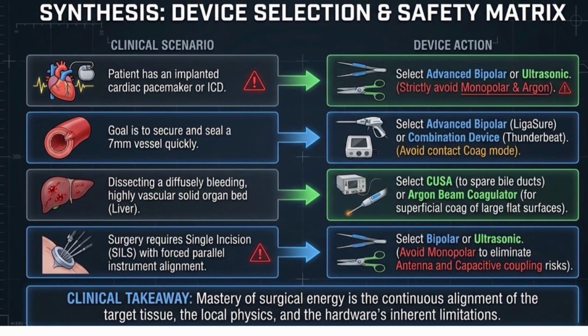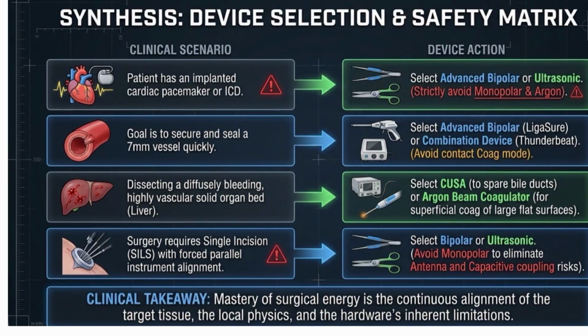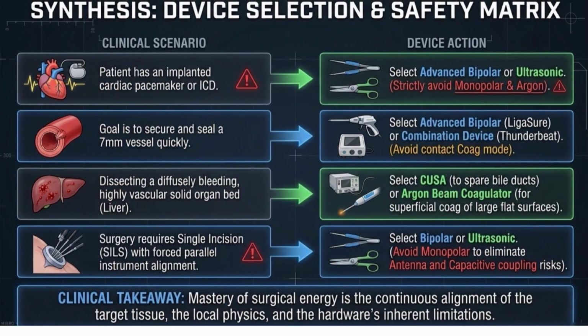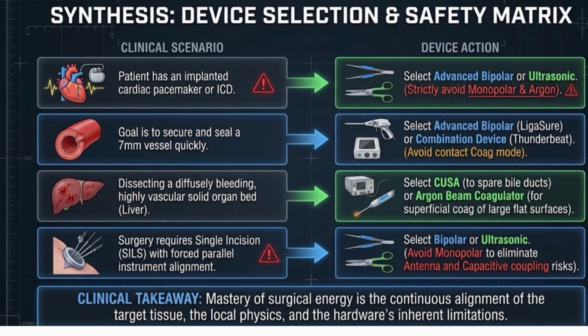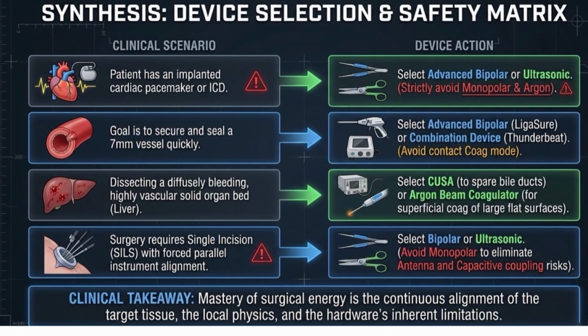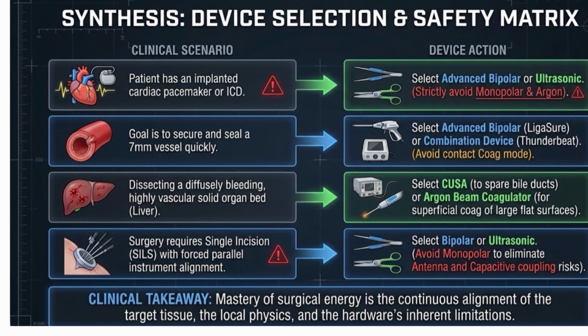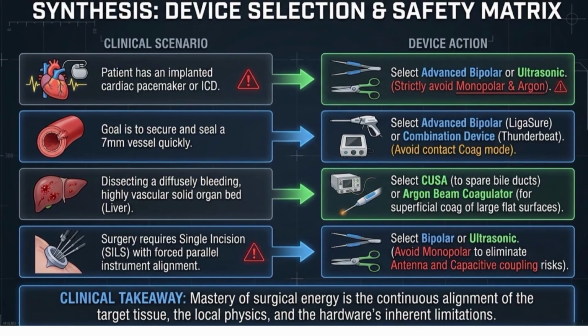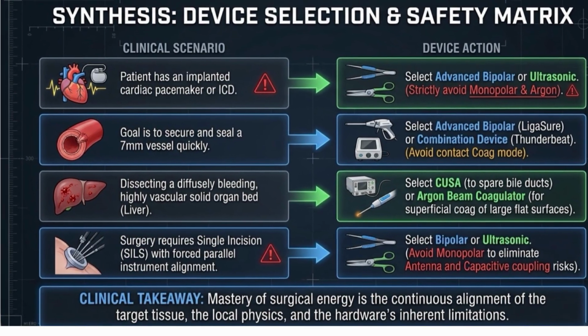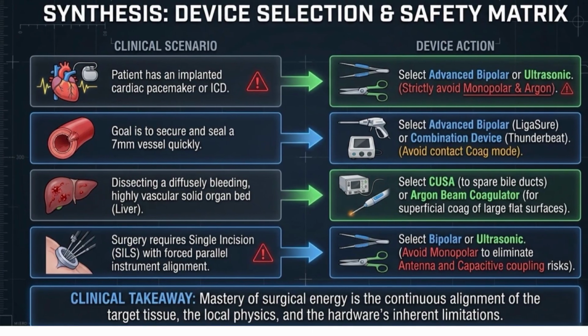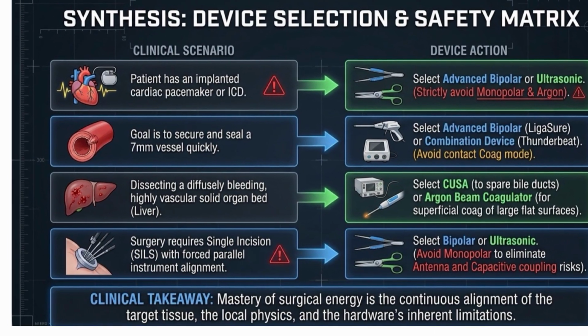A clinical scenario and the device activations. For patients with an implanted cardiac pacemaker or ICD, select advanced bipolar or ultrasonic, and strictly avoid monopolar or argon. To secure a seal of a 7 mm vessel quickly, select advanced bipolar LigaSure or a combination device, Thunderbeat. Avoid contact coagulation mode.